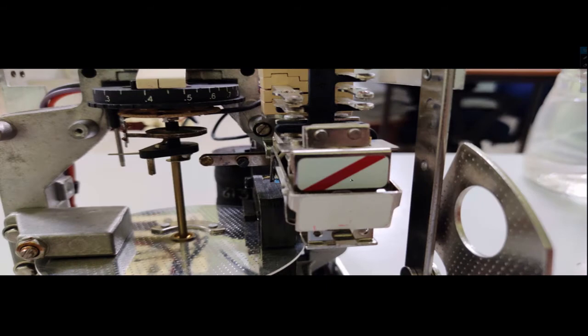And this is called the flag of the relay. After every operation, on the relay flag, if you see this type of symbol, that means the relay has already generated the trip signal, and the circuit breaker has disconnected the faulty portion from the system. After manually clearing all these things, you need to manually pull it off. So this means the relay actually generated the trip signal. Before the next operation of the relay, every time the flag goes down, you need to pull it back.